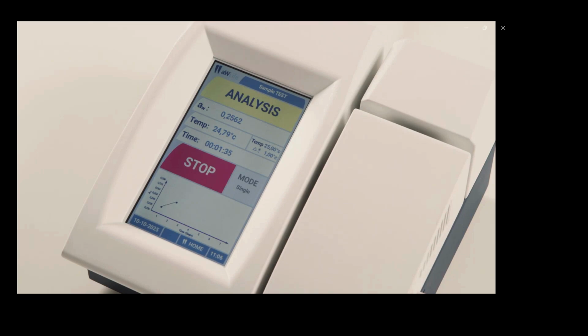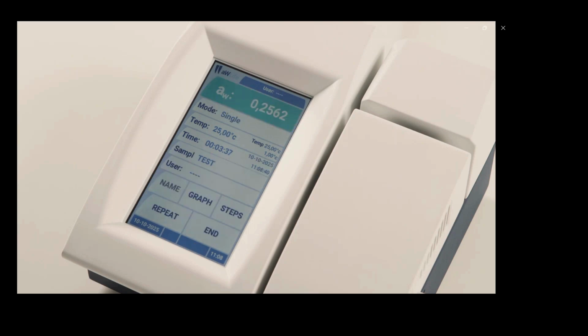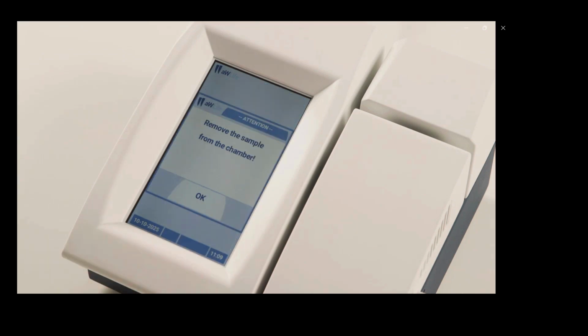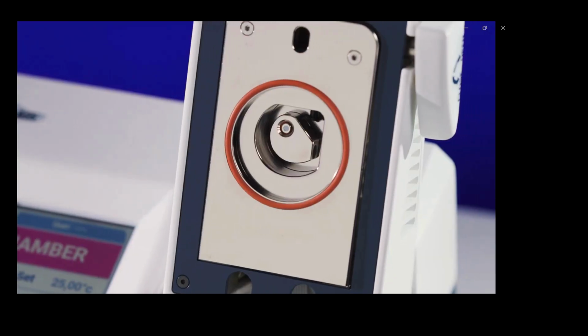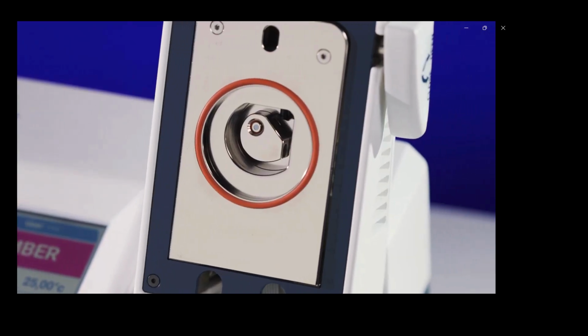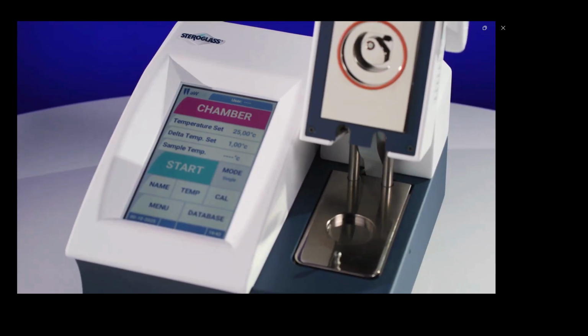The display shows a graph tracking the reading in real time. The system automatically performs a series of measurements until it obtains 3 consecutive values that are very close to one another, with an accuracy of 1/1000th. At the end of the analysis, a green light shows that it was successful. Press Finish, then remove the sample from the chamber. Thanks to the dew point sensor, aWLife ensures precise and reliable results in approximately 5 minutes.